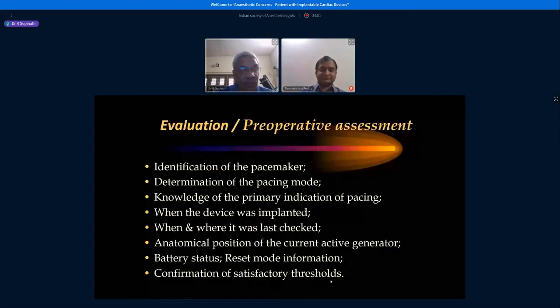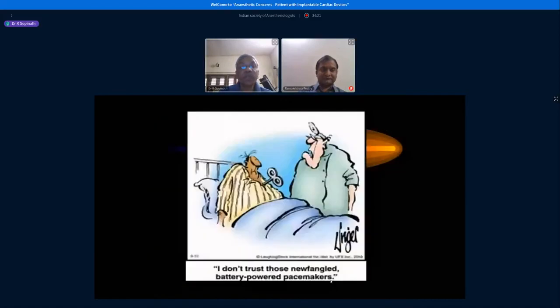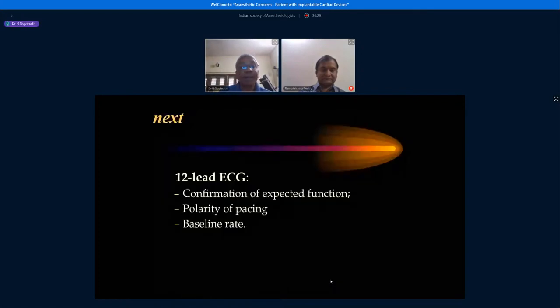But as time passes, there is some fibrosis around the lead tip and it gets implanted. That is why they are constantly interrogated over time. I'll show you in the next couple of slides the routine for doing it, before the final amount of current and the resistance are recorded, and the current and the programs are set. There is always a problem when you use battery powered ones because the source can fail.